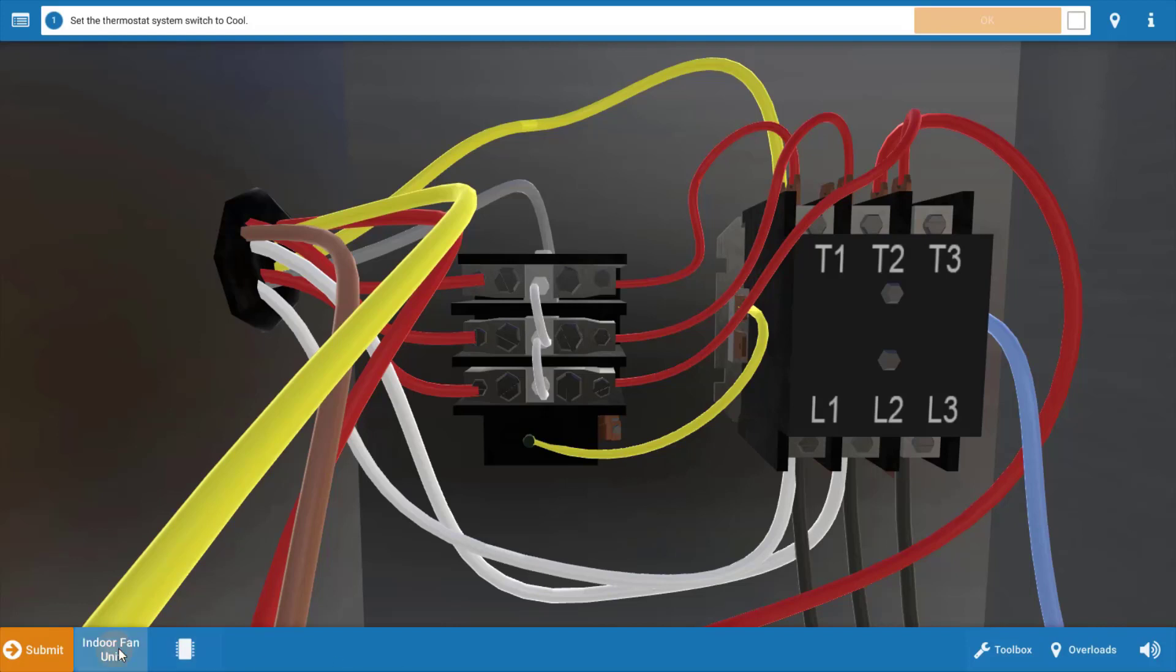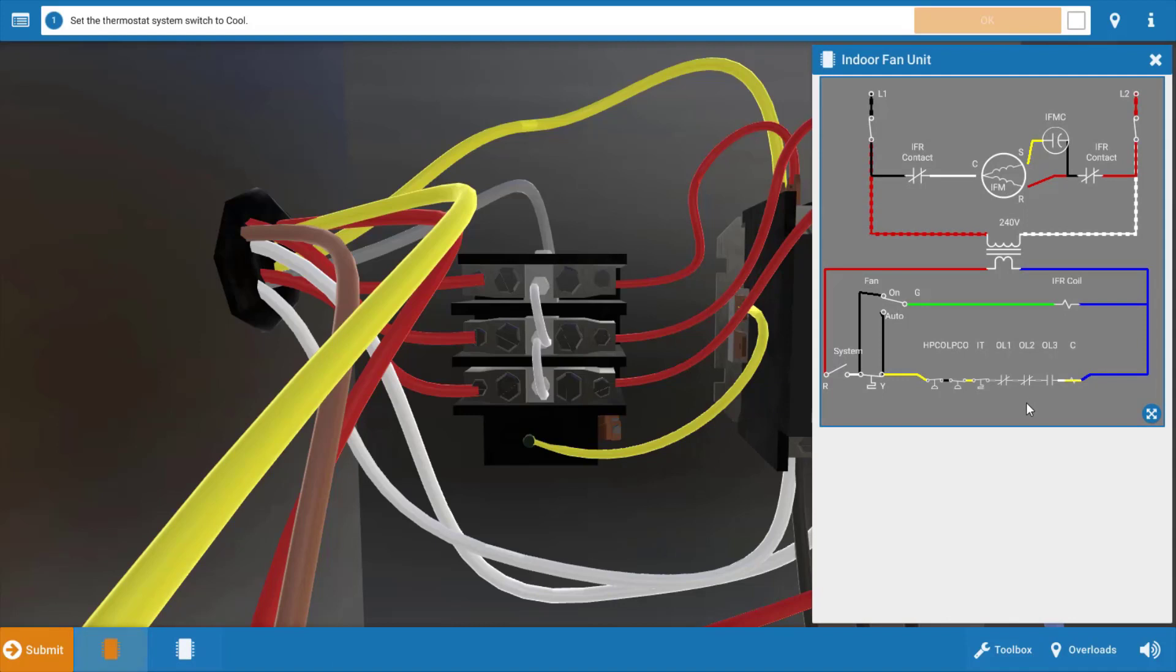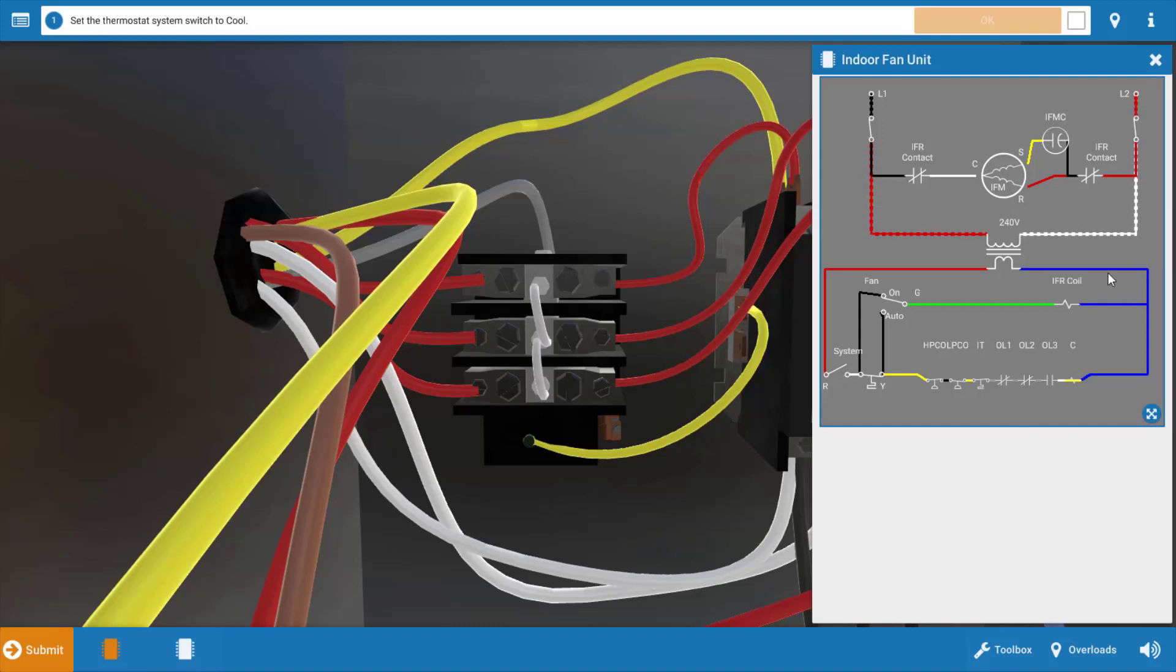Let's take a look at the diagram for a second. We can see the three overloads right here in series to the contactor, and again these would be influenced by the temperature of those heaters, which in turn are influenced by the current draw on each leg.